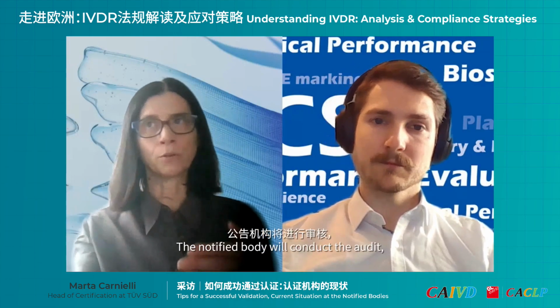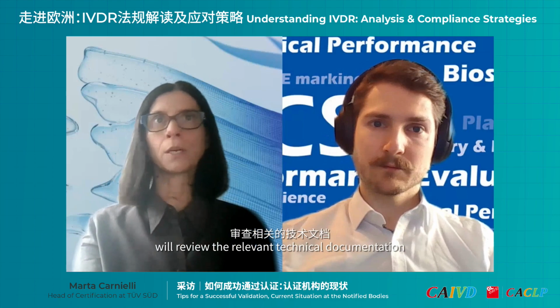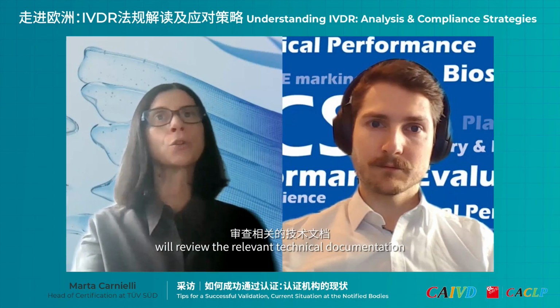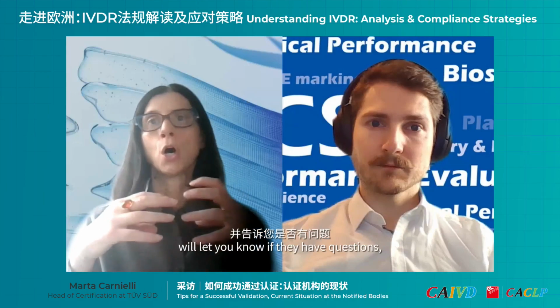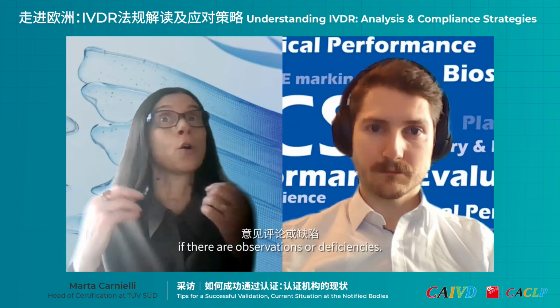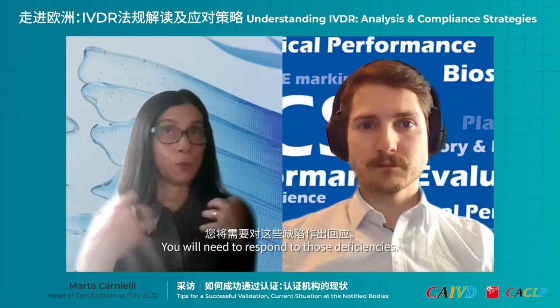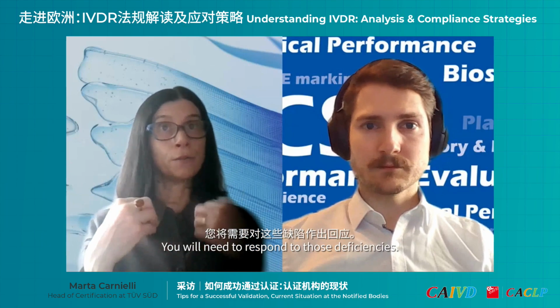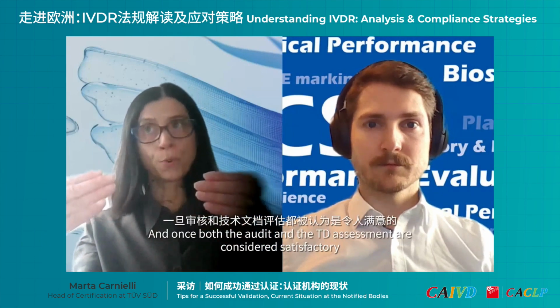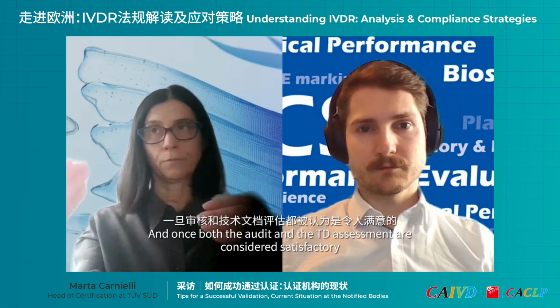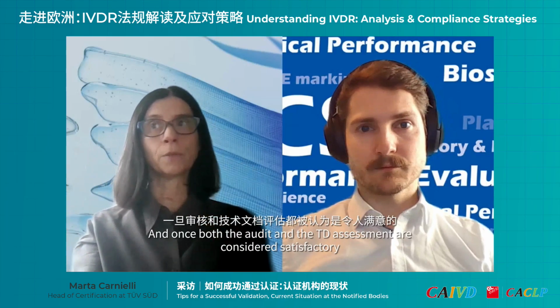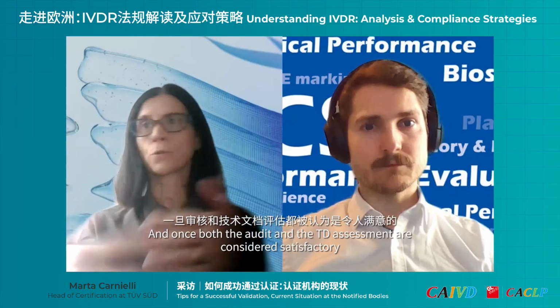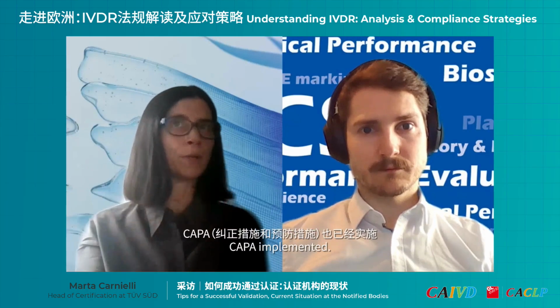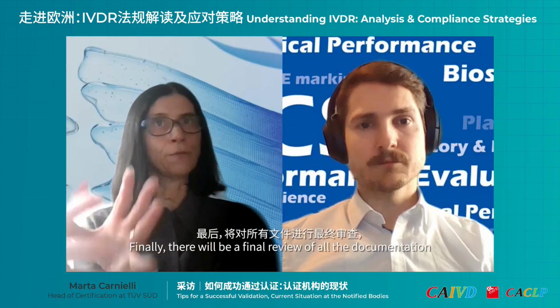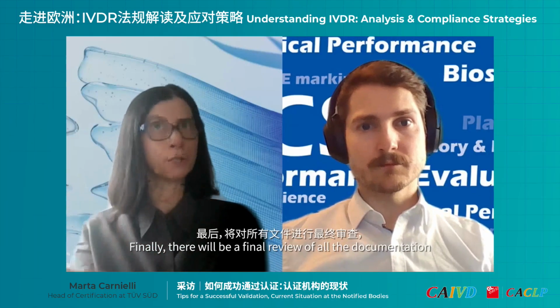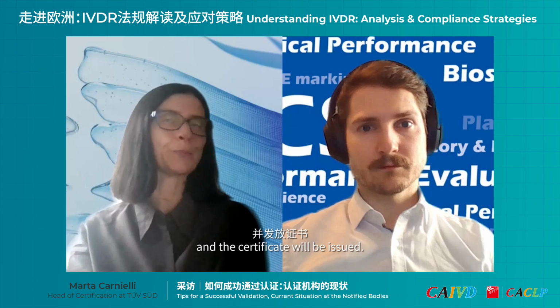The notified body will conduct the audit and review the relevant technical documentation, and let you know if they have questions, observations, or deficiencies. You'll need to respond to those deficiencies, and once both the audit and the TD assessment are considered satisfactory, with all deficiencies closed and CAPAs implemented, there will be a final review of all documentation and the certificate will be issued.